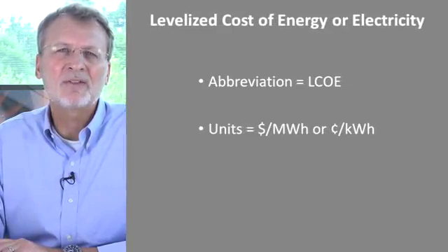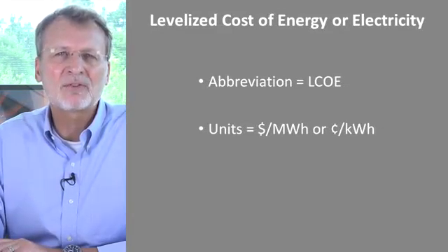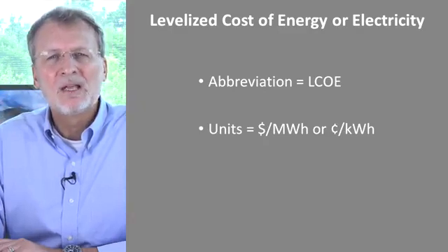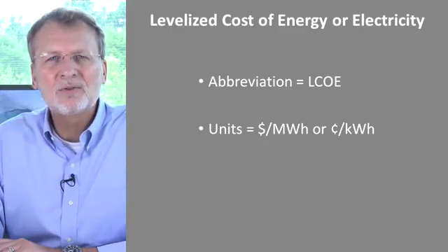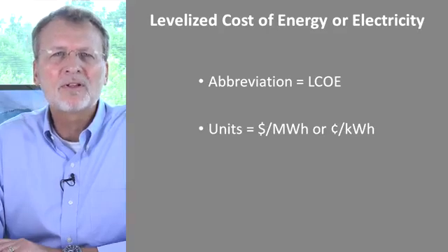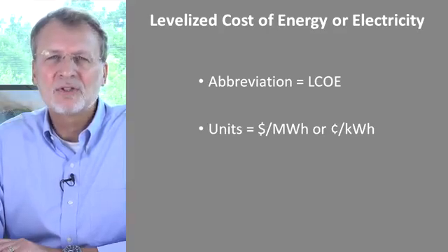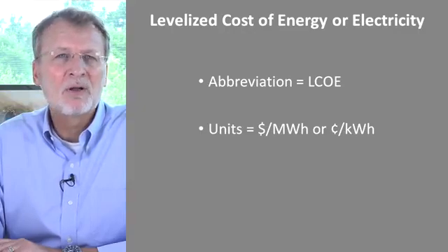However, one can compare overall plant costs by recasting the absolute cost for a plant in terms of what is known as the plant's levelized cost of energy, or LCOE. The LCOE is the plant's cost to generate a single unit of electricity over the lifetime of the plant, and it's generally given in terms of dollars per megawatt hour or cents per kilowatt hour.